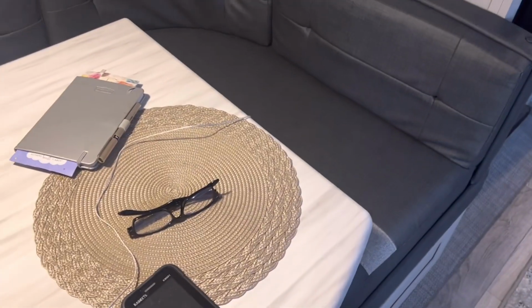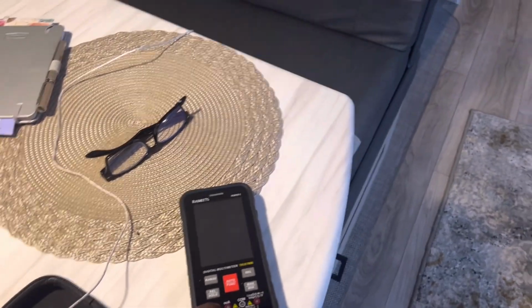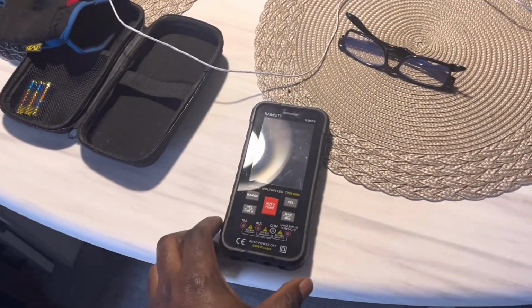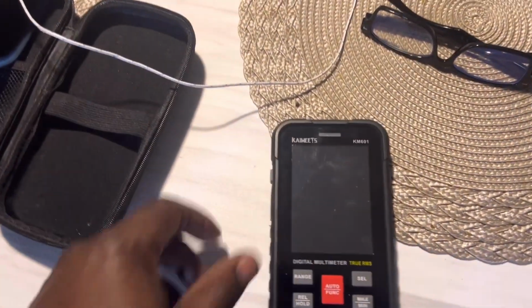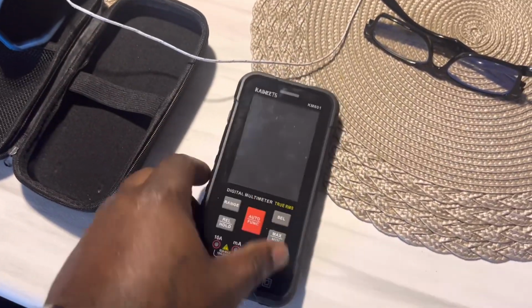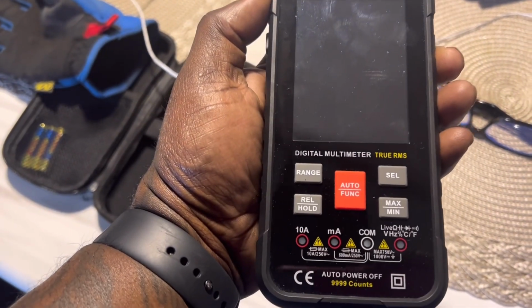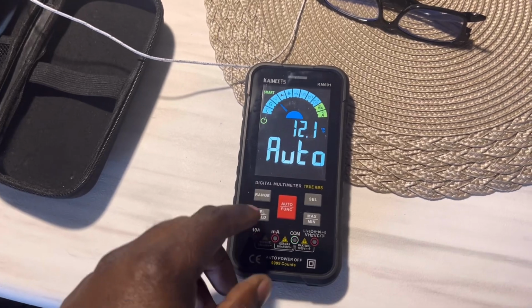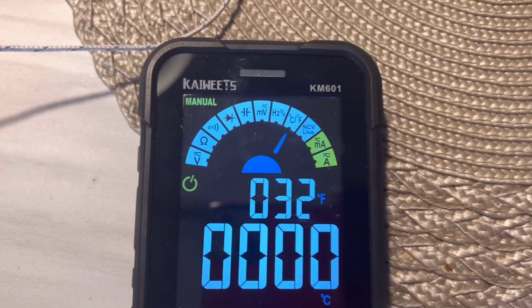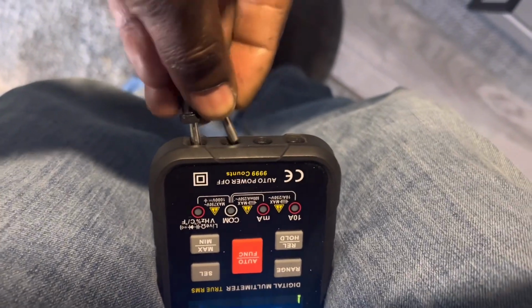Okay, beginning the performance evaluation of the AC unit. Performance test starts with taking temperature readings of ambient temperature versus discharge temperature, your supply, and performing a calculation to come up with your delta T. I'm using the Kaiweets DMM with measurements of temperature. It has a temperature function. Start off by turning on the meter and then set it to temperature. On this meter, it will tell you where to hook the probes. So it's flashing for the probes to be connected here. I'll just connect them where they go, red and black.